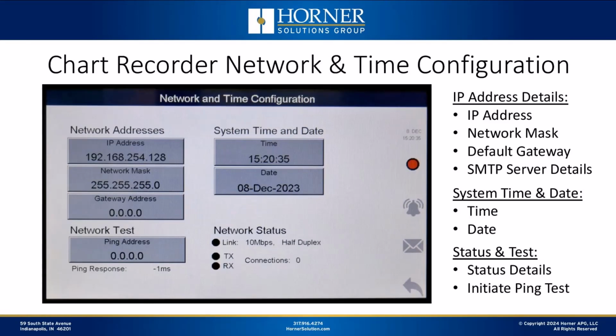So if you're going to take advantage of the networking capability, the Ethernet capability, then of course you need to configure its IP address and network mask and any default gateway if the unit needs to exit the local facility and go through a firewall or something. And of course you need to have the facility to change time and date because this guy is going to, of course, be time stamping things as you go.